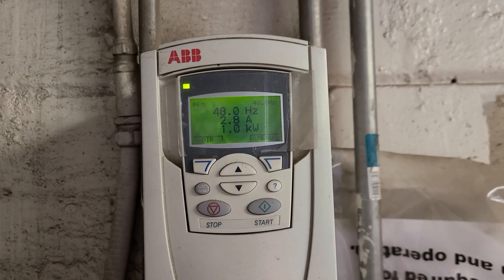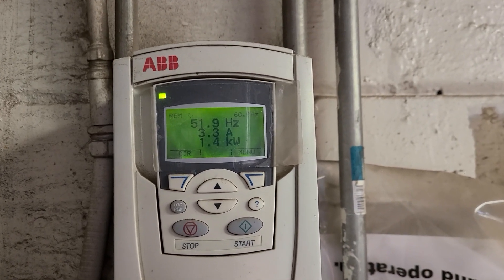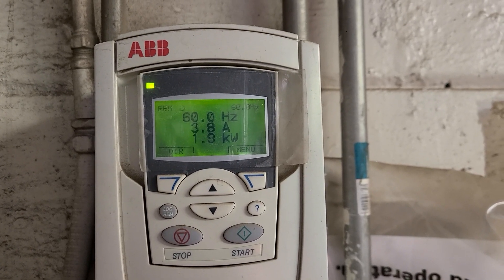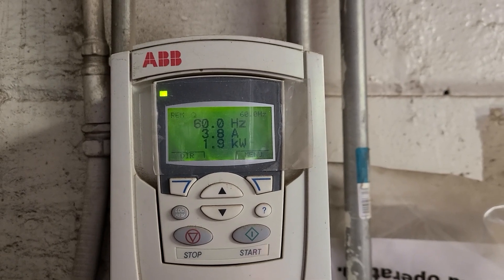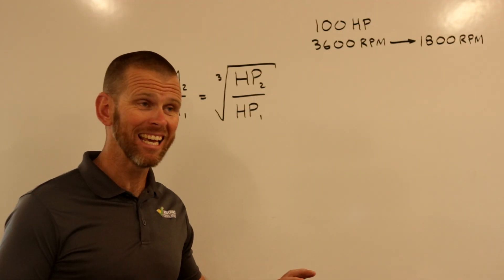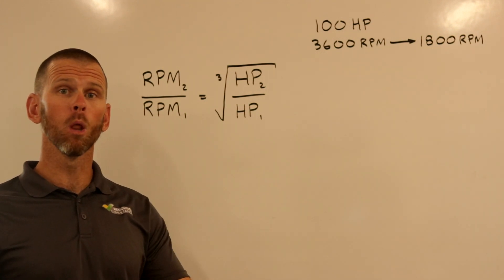A more energy efficient option for screw compressor capacity control is the utilization of a variable frequency drive or VFD on the compressor motor. VFDs modify the frequency of the power supplied to the motor, which in turn lowers the rotational speed. The beauty of VFDs is that the power consumption varies as a cube of the motor speed. This means that if we reduce the motor speed to one half of the design speed, the power consumed will be reduced to one over two cubed or one eighth of the original power.